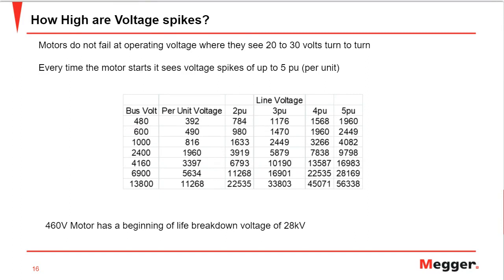But if we look at a 13.8 kV motor, it goes up to 5 times the per unit value, which is 56 kV, a very high voltage. But this is the voltage which a motor experiences, as previously mentioned, during transients or voltage spikes. That's why we do different types of high-pot testing and surge testing to analyze where the motor stands on our insulation curve. We start with the DC high-pot test.